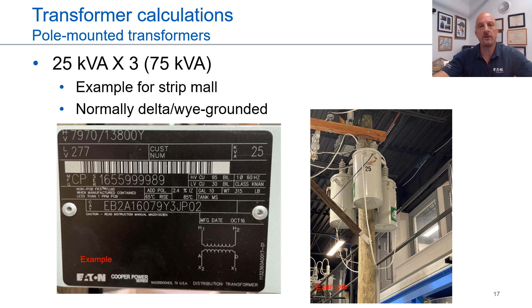What's interesting about pole-mounted transformers is they do have a lower impedance. So we made an assumption earlier, if you didn't know the transformer impedance, you could say 5.75%. But in this case, if you don't know the impedance of a pole-mounted transformer and you guess that high, guess what you're going to do? You're going to influence your fault current calculation. So it's important that you don't overestimate the impedance of a pole-top transformer. And so if I don't know the value, I might even guess 2% for that one. So 2 to 3% is a typical number.